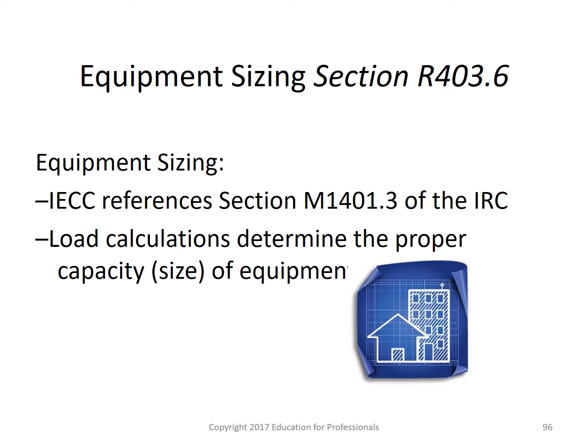And some keys to obtaining the design efficiency of a system in the field include sizing the system for the specific heating and cooling load of the building being built, and bearing in mind that one size does not fit all. A proper load analysis needs to be performed for the HVAC system to operate in an efficient and predictable manner. This includes the selection and proper installation of thermostats and controls, and a ductwork system designed to deliver the correct amount of air-conditioned air to each space within the building. And of course, going back to what we mentioned before, the insulating and sealing of all ductwork.